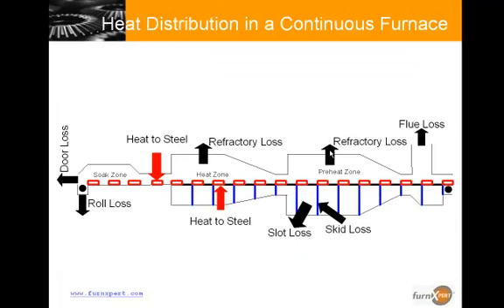Now I am going to talk about heat distribution in a continuous furnace. All the heat from combustion does not go into heating the steel charges. If it did, it would have been a 100% efficient furnace. The heat that is not utilized in heating the product is known as heat losses as shown here by black arrows. Different losses are door loss, roll loss, refractory or wall loss, slot loss, and skid or water loss. And finally there is a flue loss which is the heat that escapes from the furnace with the flue gas.